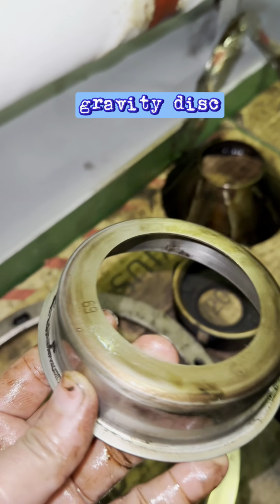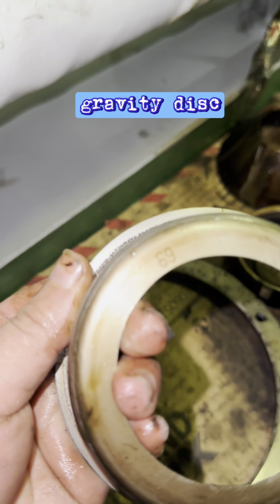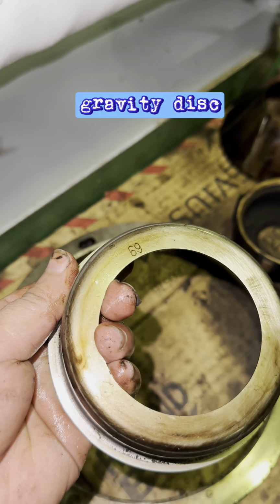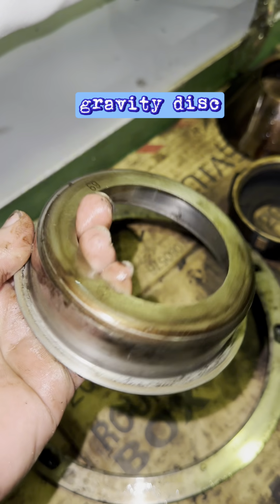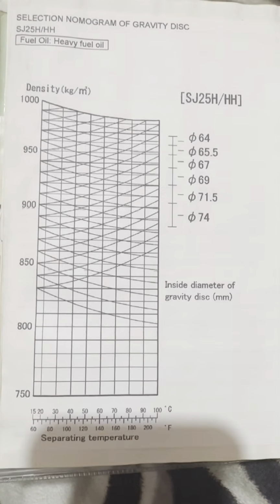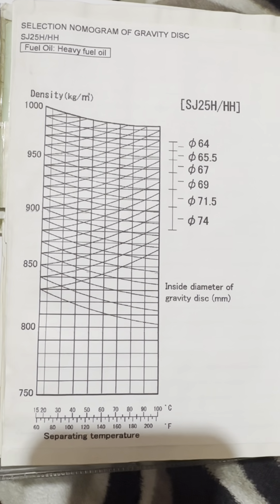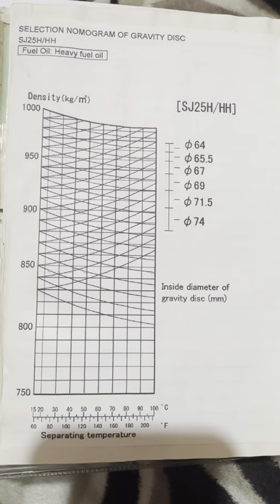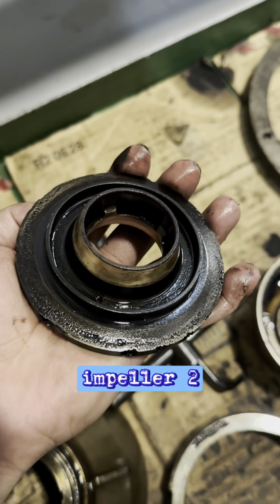Gravity disc, used to maintain correct interface between the oil and water. The purpose is to fit for purifying oil of different specific gravity. To determine the correct gravity disc, use the nomogram provided in the manual instruction.